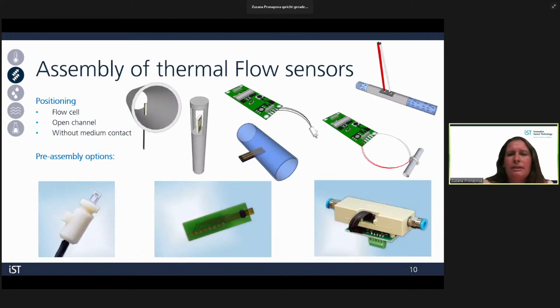So how should this type of flow sensor be integrated into a flow channel? As you'd expect, the better defined the geometry and resulting flow profile, the easier it is to evaluate the signal afterwards. Since we correlate mass flow to heat dissipation, we again face a construction task: getting close to the medium while insulating the sensor from the housing.